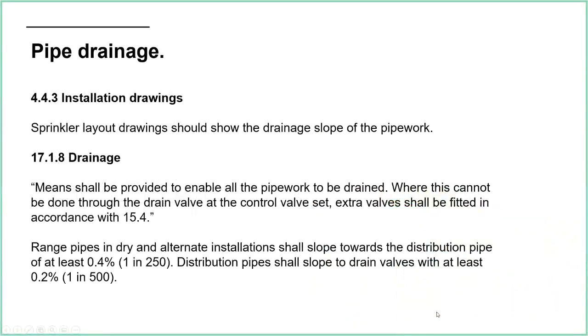Drainage. Okay, so let's talk about drainage now. So again, we've got quite a nice catch-all statement here. First of all, the sprinkler layout drawings should show the drainage slope of the pipework. Okay, so that's something that needs to be thought about from the design stage. But this is my catch-all statement here: means shall be provided to enable all pipework to be drained. Okay, so every single bit of pipework, ideally, should have the ability to be drained.